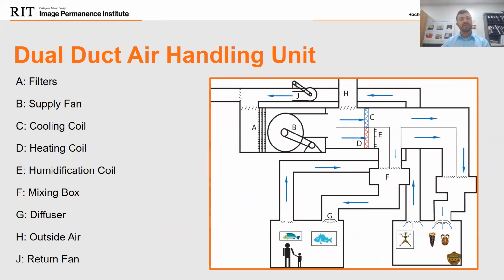It's a dual duct. So as I showed you that unit earlier that had subcool reheat, now imagine that our air is going to return from this unit and come back. And then we're going to pass it over some filters. Our filtering is done here. And again, this is our outside air. It could be located here. We've seen it located here. We've seen it located here. But we're going to bring some outside air in. We'll mix. And now the air, once it leaves the unit, splits in two.